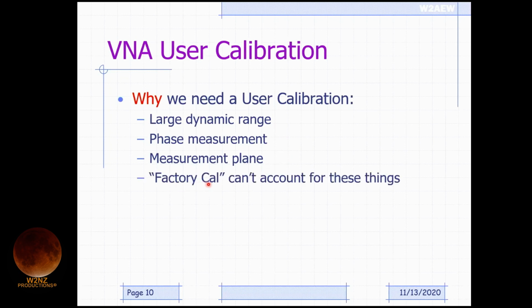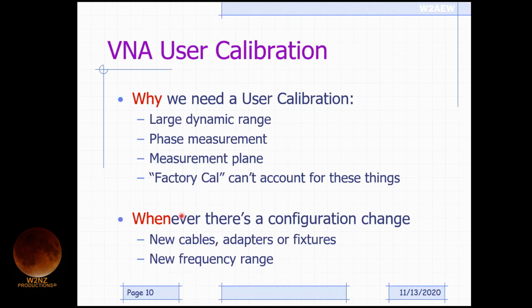Of course, a factory calibration can't account for all of these things, because it doesn't know how you're connecting things up and where you want to establish that reference plane. And there are a number of little nonlinearities that are always going to be systematic errors that you want to take out when you can. So this is why we run a user calibration. It really enhances the instrument's regular calibration and can establish that new measurement plane at the connection point for your device. So when do we want to do a user calibration? Whenever there's a configuration change, meaning I'm changing my cables or adapters, changing a fixture I'm using to measure a device, or changing the frequency range I'm making a measurement on.